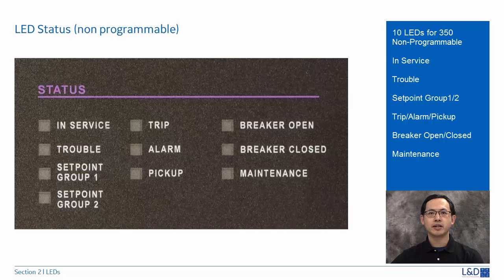Trip LED will turn on to red color when the relay detects a fault and sends a trip command to the trip output relay. The LED will reset by reset push button or the software when the fault condition has cleared.